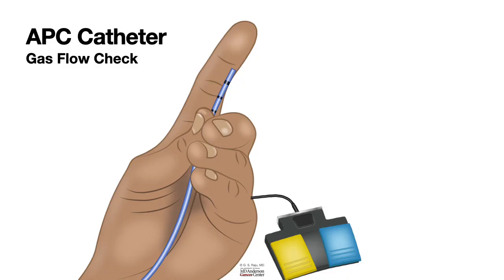To check gas flow, press the blue pedal and feel the gas on the tip of your finger — if you feel it, you are set. In previous models, people used a separate system to check whether the circuit was complete, but that is now part of the machine.